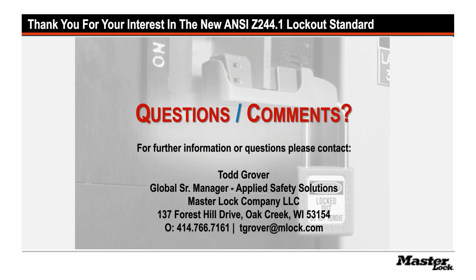You know, Tom, that's a good question. And just the way it was laid out there, it talks a lot to the auditing process. So let me just talk to that, and I'll talk to it from the ANSI standpoint as well as the OSHA. What is critical is that there is an observation made, at least on an annual basis, of the performance of personnel to meet the expectations set by the lockout program and indirectly by the procedure that they are following at the time they're being assessed.